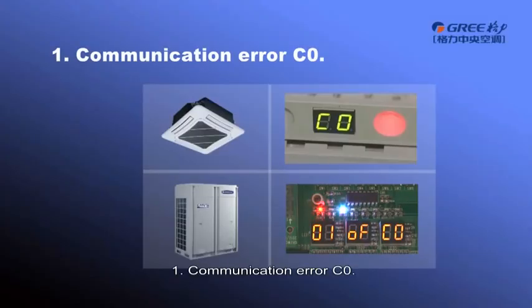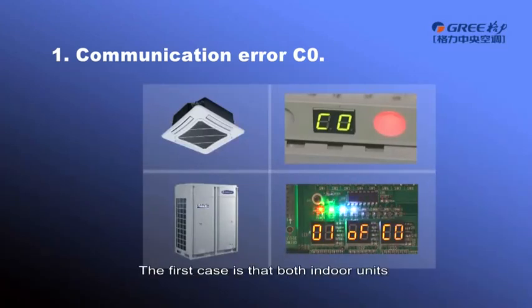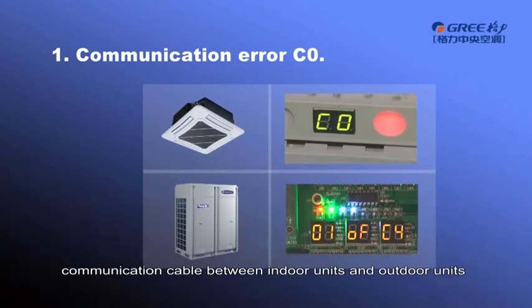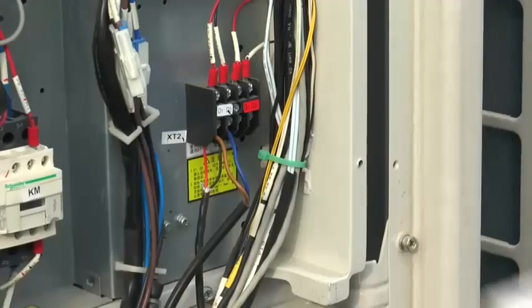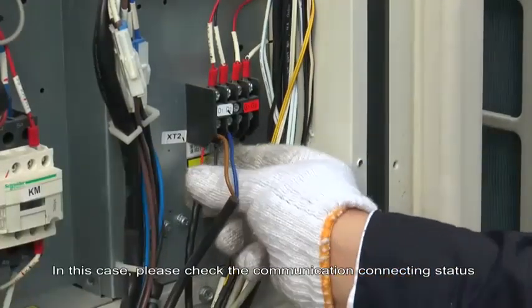First, Communication Error. There are two cases for this error. The first case is that both indoor units and outdoor units display C0, which means the main communication cable between indoor units and outdoor units is broken or disconnected. In this case, please check the communication connecting status.